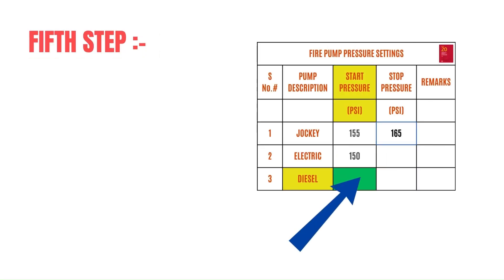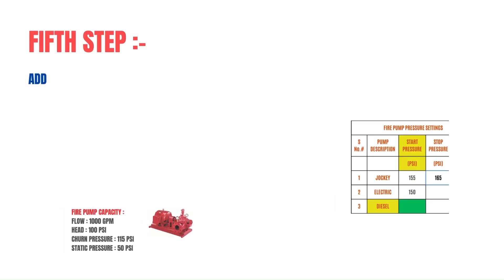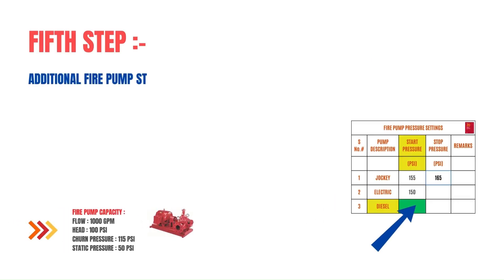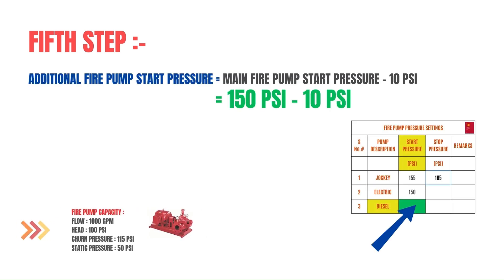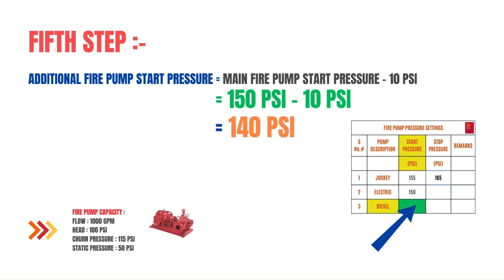The fifth step is calculating the start pressure for the diesel fire pump. If we have an additional fire pump, we reduce 10 psi from the main fire pump start pressure. As you can see on your screen, the additional fire pump start pressure equals the main fire pump start pressure minus 10 psi, giving us 140 psi.